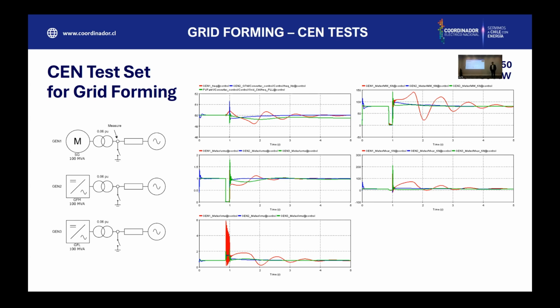Yes. Well, you cannot see because of the symbol, right? Yeah, I can see it on the projection online. Okay, thank you. So it was 80 megawatts, each one of them in their own isolated systems, and short circuit ratio 1.5.